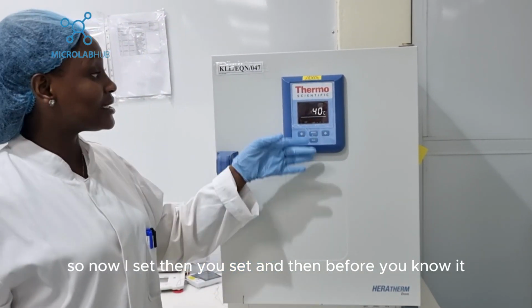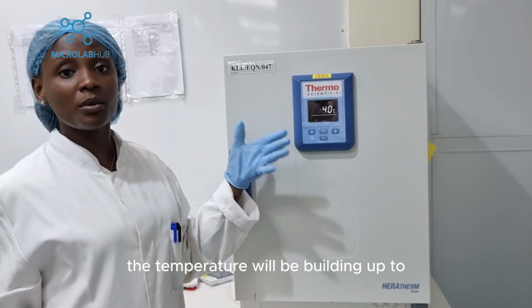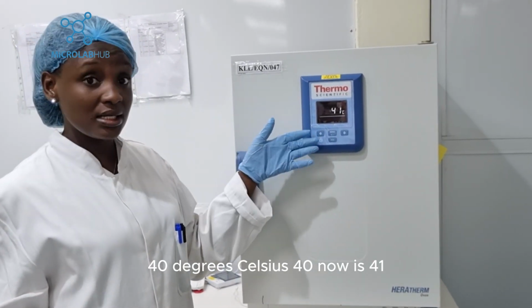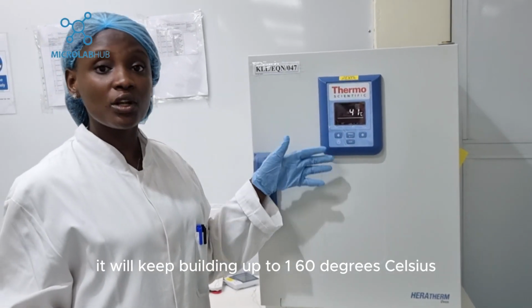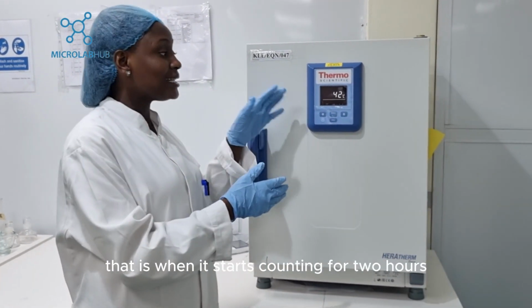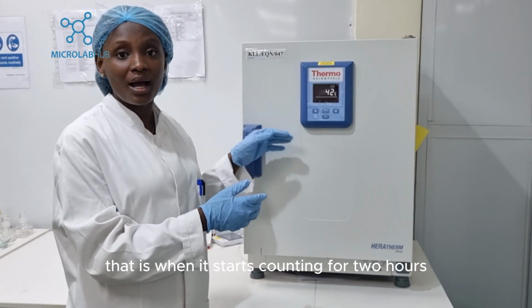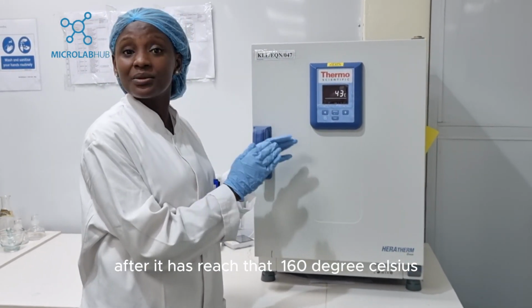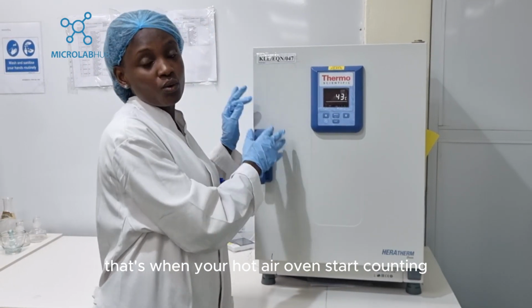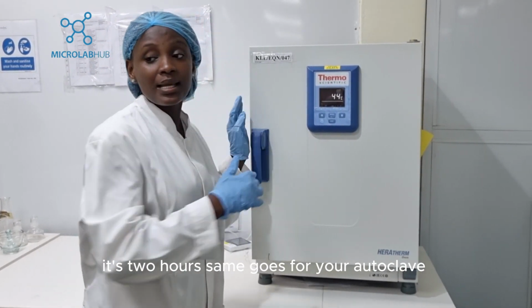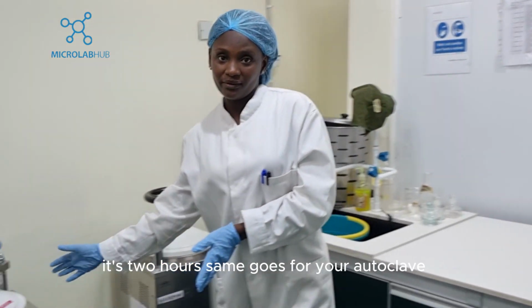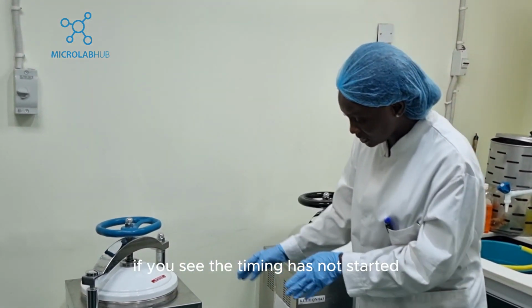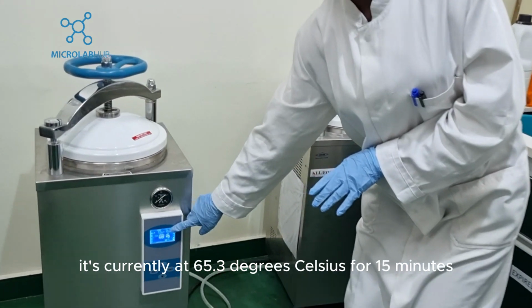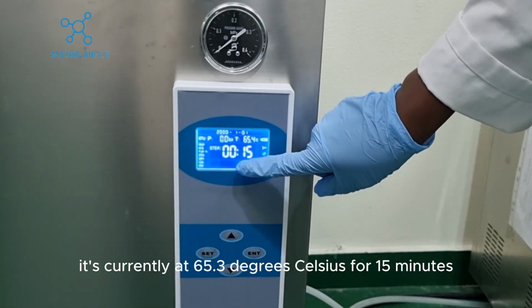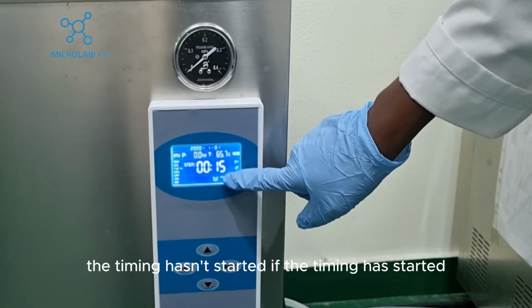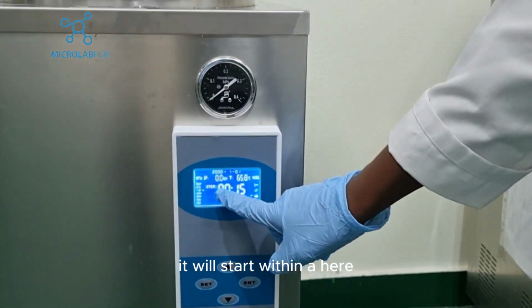Before you know it, this you see is already increasing. The temperature will be building up, 40, now it is 41. It will keep building up to 160 degrees Celsius. That is when it starts counting for 2 hours. After it has reached 160 degrees Celsius, that's when your hot air oven will start counting its 2 hours. Same goes for your autoclave here. If you see the timing has not started, it's currently at 65.3 degrees Celsius for 15 minutes. The timing hasn't started. If the timing has started, it will start reading here.